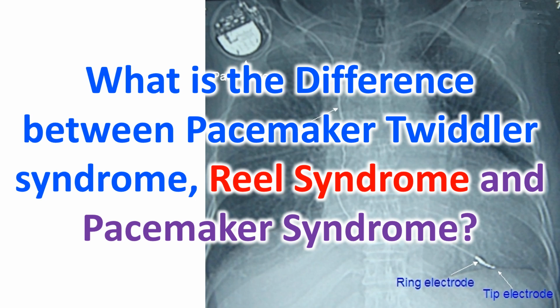Pacemaker Twiddler syndrome is characterized by coiling of the pacemaker lead due to rotation of the pulse generator of the pacemaker system along its long axis. This is seen in those with a lax skin and subcutaneous tissue, like in the elderly.